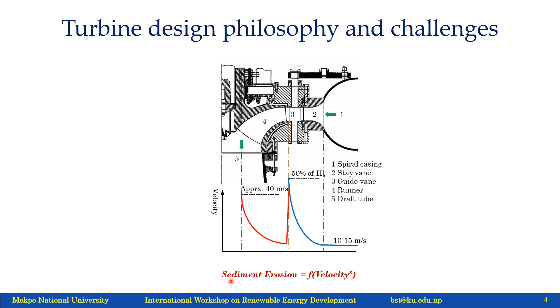From the guide vane, when the water enters inside the runner, the relative velocity starts, and the velocity field drops abruptly at the inlet of the runner, and slowly it accelerates, and again at the outlet the velocity is quite high. So you can see that at the guide vane and at the runner outlet there are two velocity peaks. And when it comes to the sediment erosion, it is related with the cube of velocity, so if the velocity is increasing by twice, erosion will be increasing by 8-fold, and that makes the standard Francis turbine, very efficient in clean water, a big problem in water with sediments.